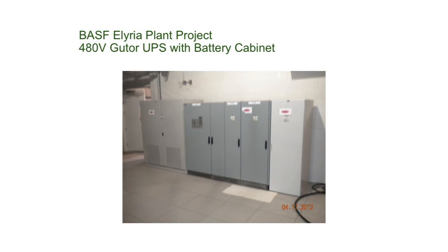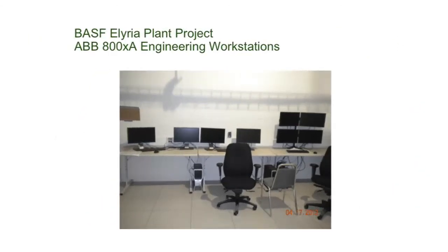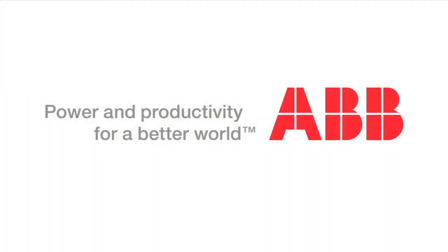And this is the engineering control room. So this isn't the actual operator control room for the facility, but this is where we installed our clients for the engineers to sit during commissioning and startup, which is just off of the main electrical room and the I/O room, where we have all of our I/O and server cabinets. All three rooms had the false floor, and all cabling, Profibus, Ethernet, power is all under the floor. And that's about it.